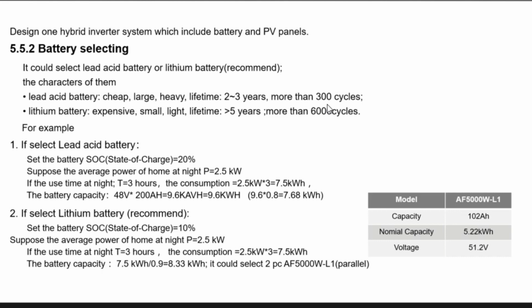When we talk about the battery, after you select the type of battery, next we need to calculate how many batteries or how many kilowatt hours of battery we need. Typically, the battery capacity is matched with the inverter size. But if the user has more consumption or needs, the battery bank should be double or even triple, depending on the consumption load they have and their energy consumption habits. So that's a point to note.